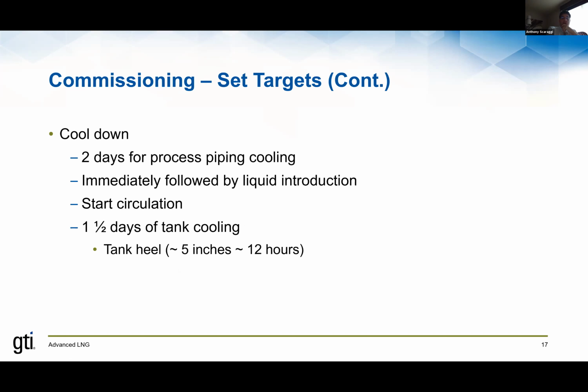Once again, setting your targets, knowing your limits, generally 2 days to cool down process piping. So to take that piping from atmospheric conditions, let's say it's 90 degrees out, and you're going to introduce minus 260 degree Fahrenheit LNG into that system, it's going to take about 2 days to initially cool down the piping. You cool it down very, very slowly. You're going to introduce those stresses associated with the piping system contracting, and possibly, if you don't do it slow enough, you risk damaging the piping systems. Once you have it cooled down, you immediately introduce the LNG liquid into the system. And in areas where you start circulation to maintain those piping systems cold.